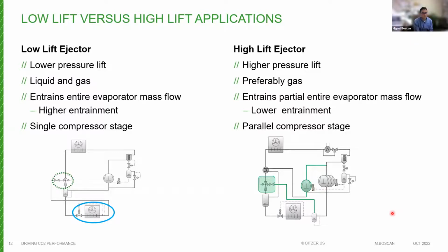Oh, I think the key takeaway is you can't run away from CO2. You've already mentioned there are other natural refrigerants as well that pose some different challenges, but natural refrigerants are the only really future-proof refrigerants. And CO2 is a great refrigerant for many different applications when the system is designed properly, and you can't beat the GWP and all the other characteristics that make it attractive going forward.